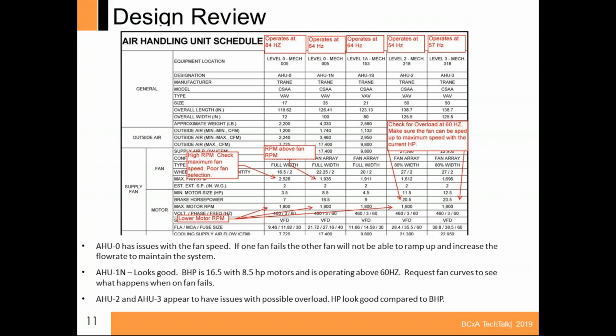So in this case, I recommended, you know, why aren't we going with a little bit larger fan and getting those RPMs down a little bit? And then that way, when one motor fails, we can actually ramp the other one up and maybe limit the maximum frequency in order to maintain as much airflow as you possibly can.